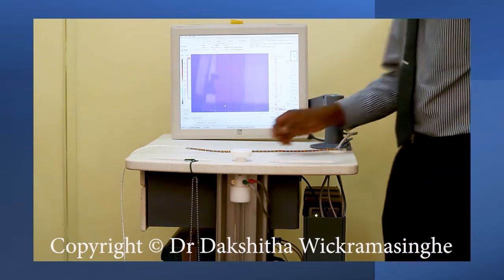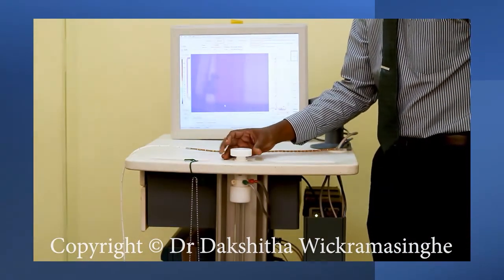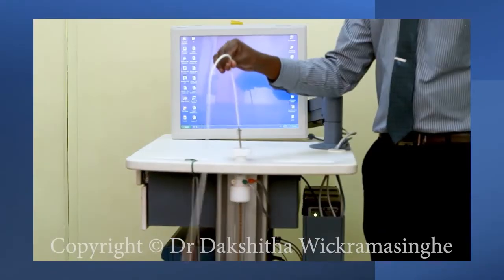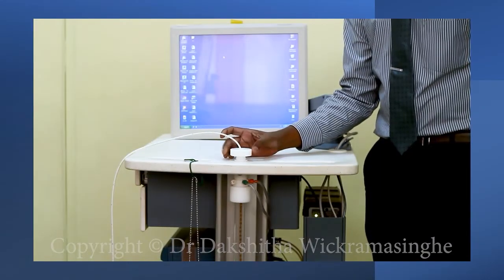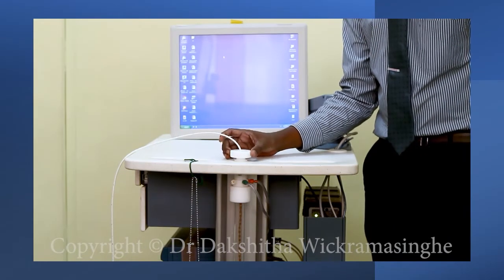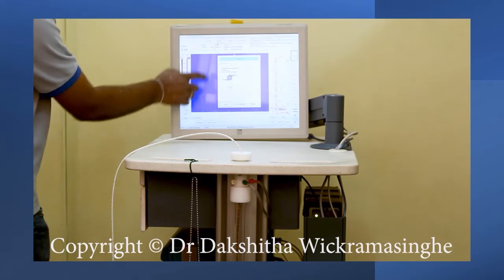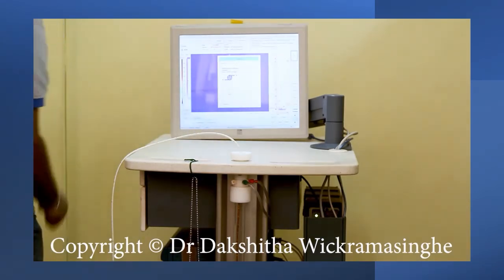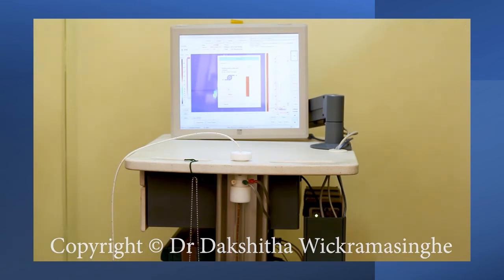To calibrate the esophageal manometry probe, first loosen the screw lid by turning it counterclockwise. Insert the catheter into the chamber until the mark indicated as Cal is at the level of the screw lid. Press the Calibrate button to enter the menu, then zero the channels and begin the pressure calibration. You will see that the pressure measured by the catheter will increase. Once the calibration is complete, the OK button will be enabled.